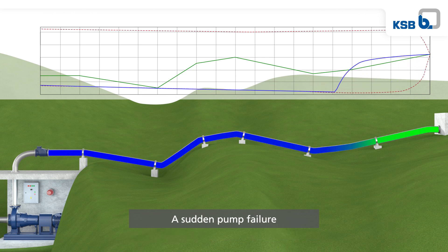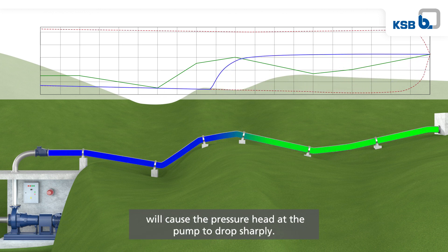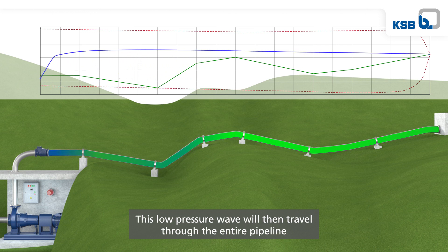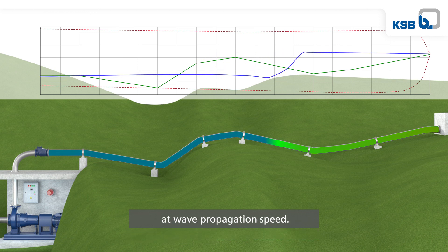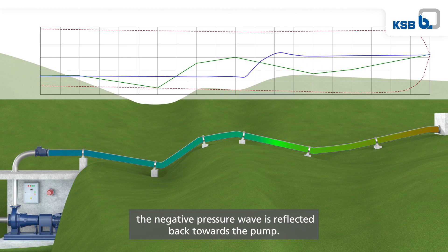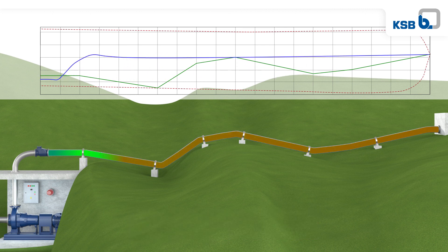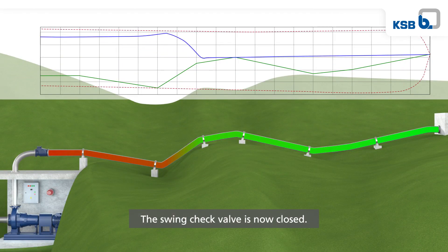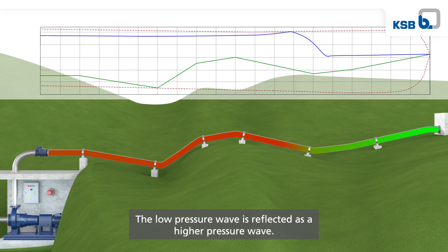A sudden pump failure will cause the pressure head of the pump to drop sharply. This low pressure wave will then travel through the entire pipeline at wave propagation speed. At the free outlet into the reservoir, the negative pressure wave is reflected back towards the pump. The swing check valve is now closed, and the low pressure wave is reflected as a higher pressure wave.